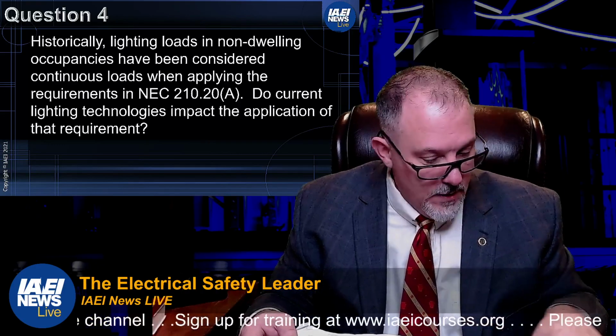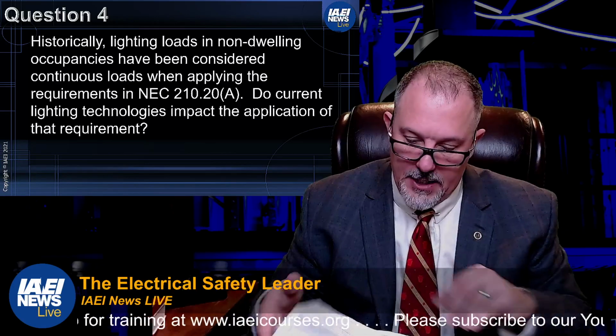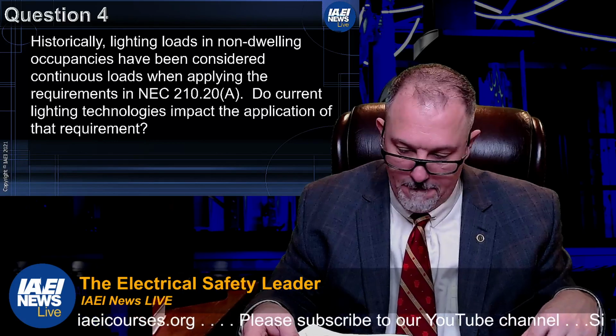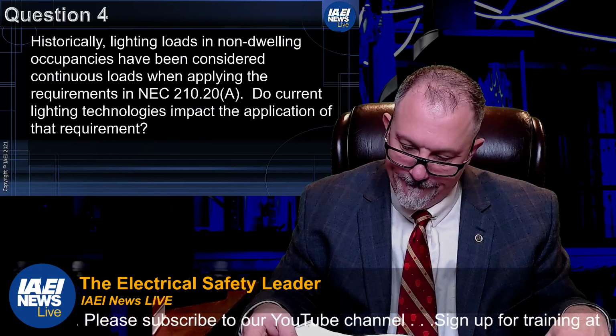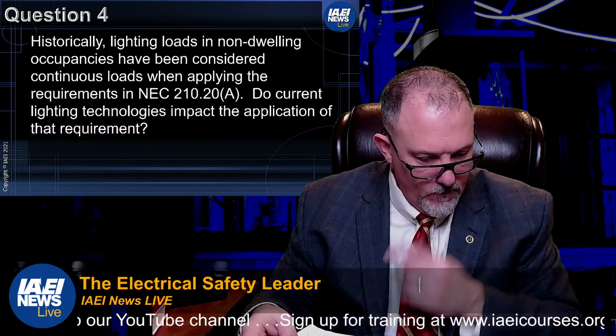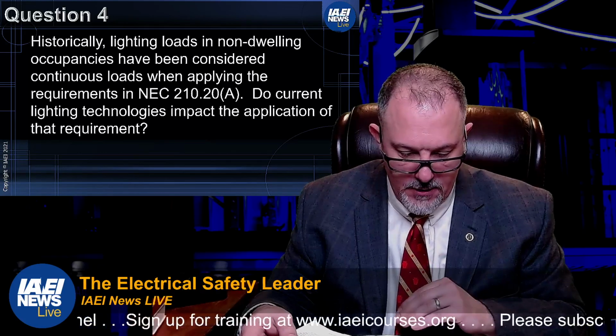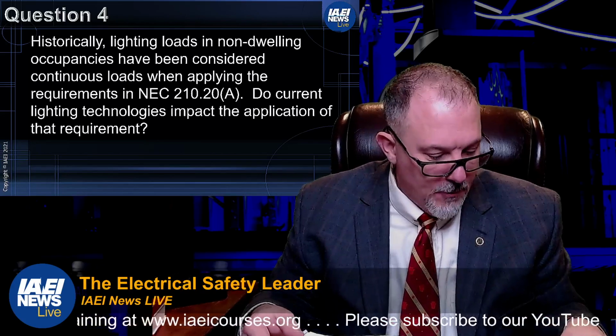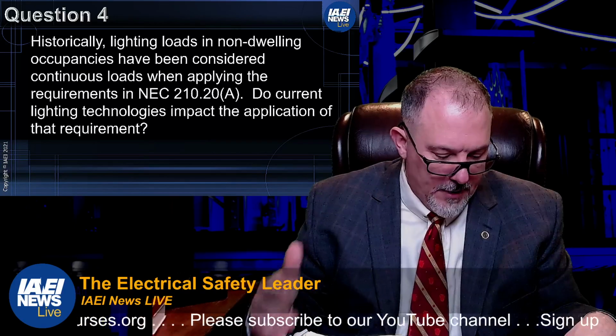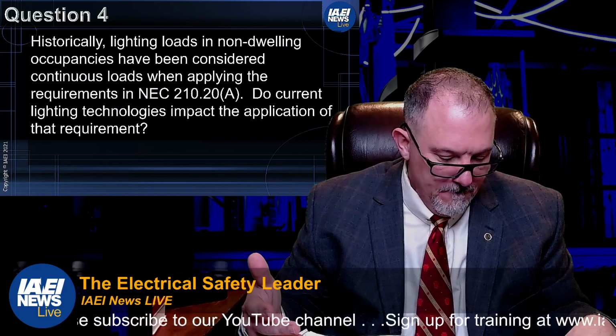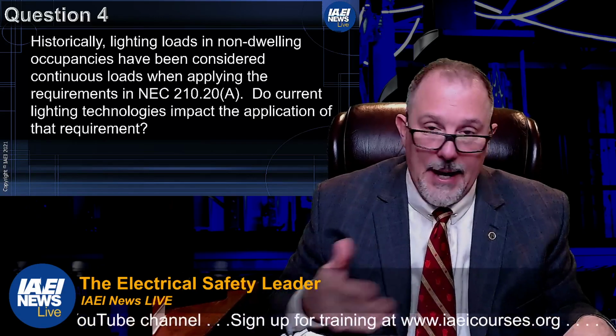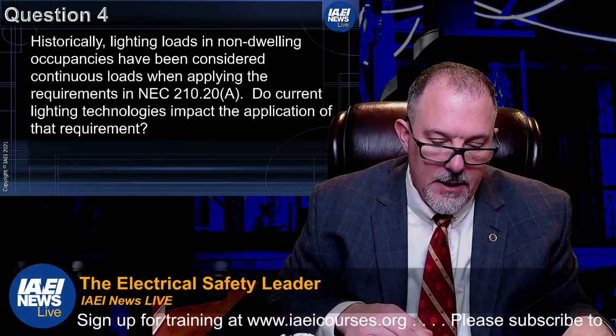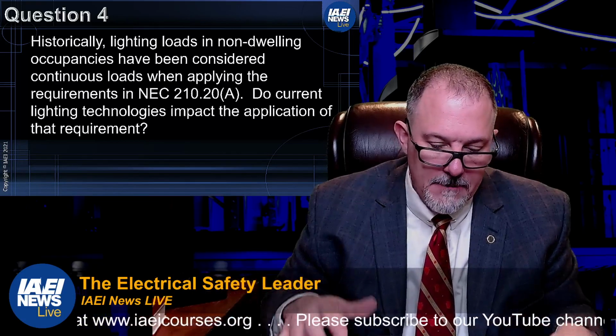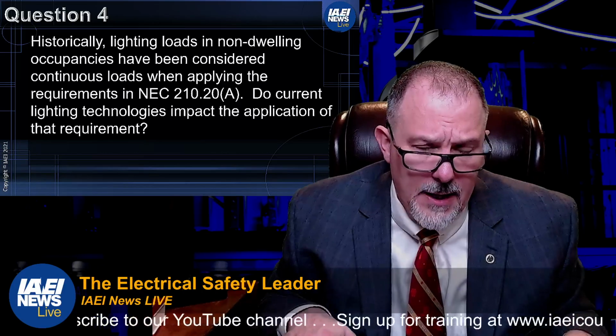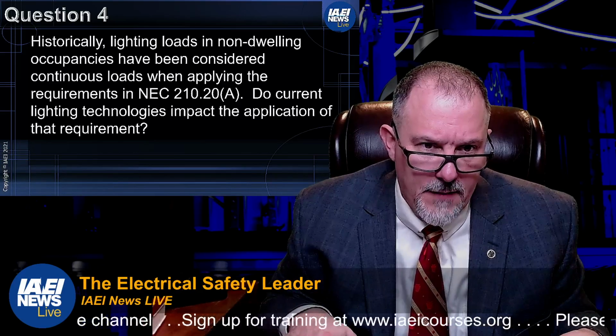210.20(A) says, what is the title of 210.20 first? Remember, we're in overcurrent protection. Overcurrent protection in branch circuits. And I believe it's Part 1. And it is, it's Part 1. 210.20 deals with overcurrent protection for the branch circuit and equipment. I want to make sure that it's protected from overcurrent based on (A) and (B). And (A) is your continuous and non-continuous. And where you have a branch circuit that supplies continuous loads or any combination, then you have to take 125% of the continuous load, right? So this is making sure that the branch circuit and equipment are protected. Now, historically, lighting loads. So do current lighting technologies impact the application of that requirement?